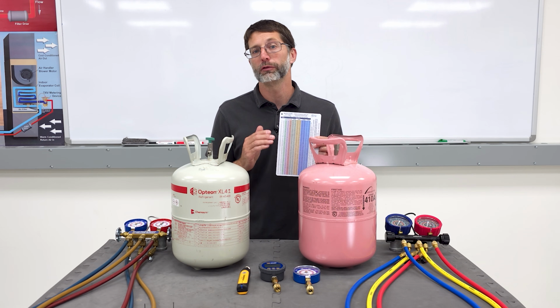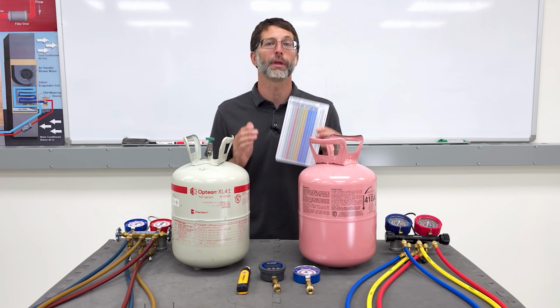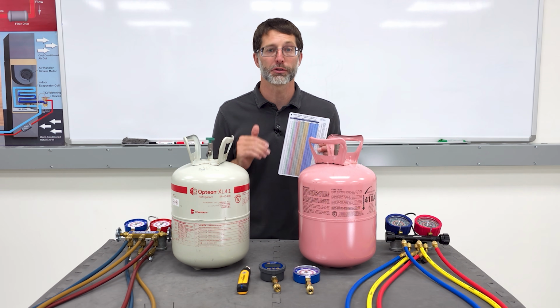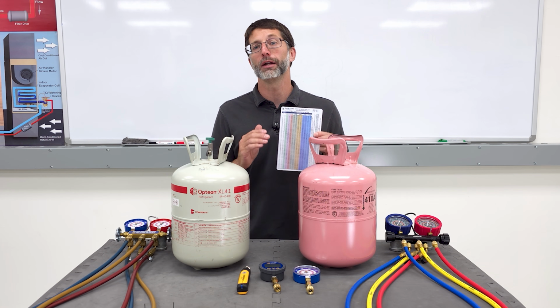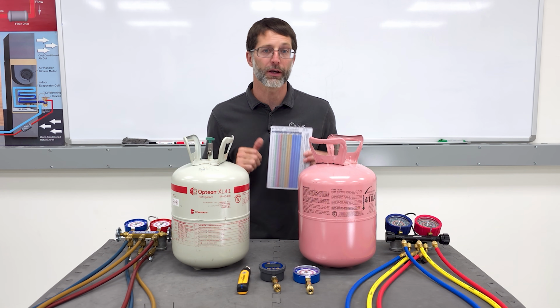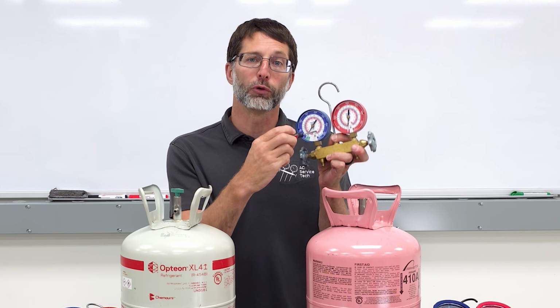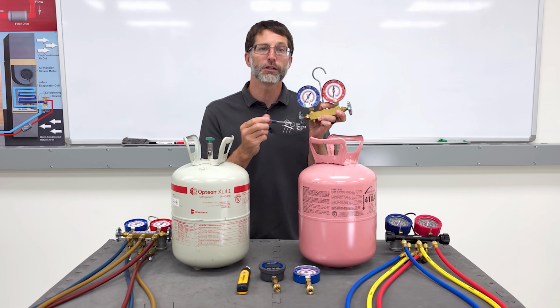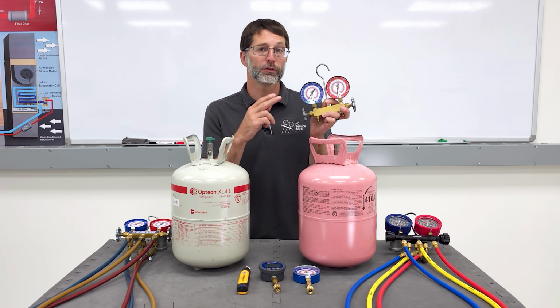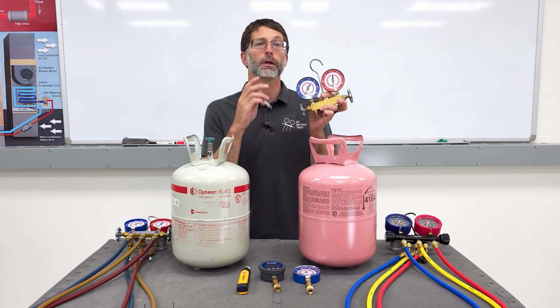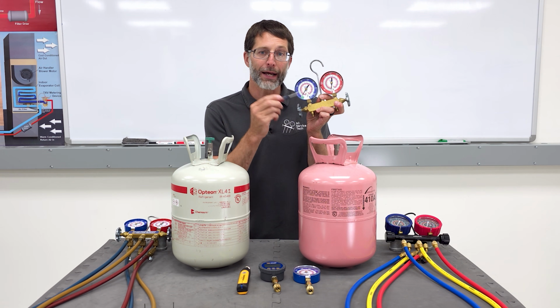Do not connect the manifold gauge set or gauge stub to a system that has a higher pressure than the max pressure rating of a compound gauge and/or a compound manifold gauge set. A compound gauge needs to be zeroed before use. If a compound gauge is used at a different elevation prior to its use, the gauge pressure must be manually zeroed with a screwdriver at the adjustment screw.